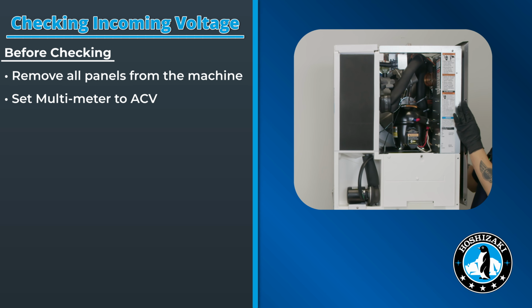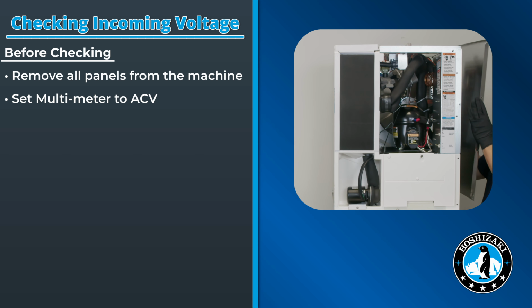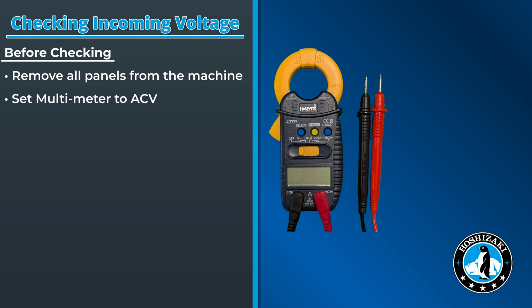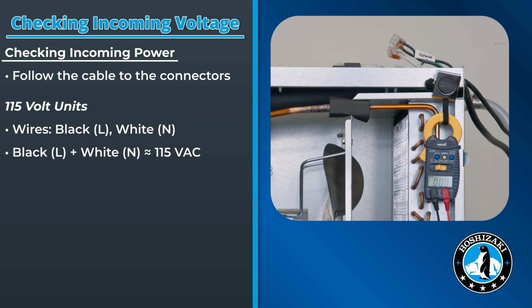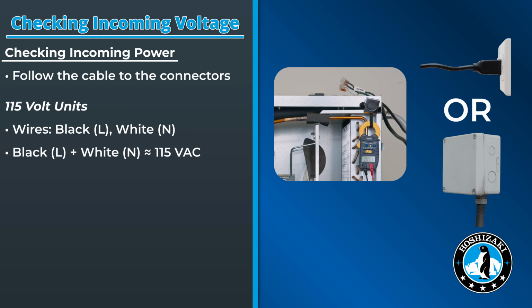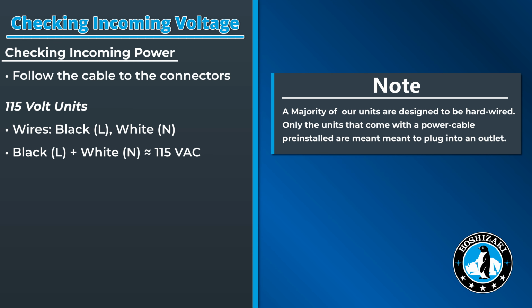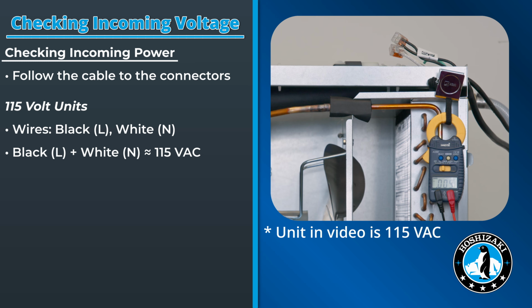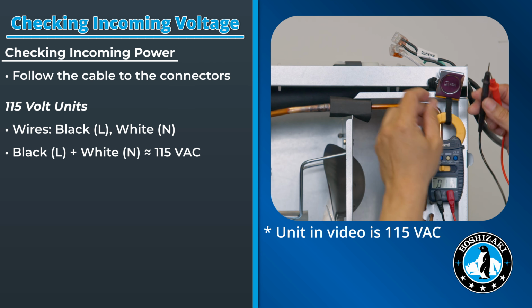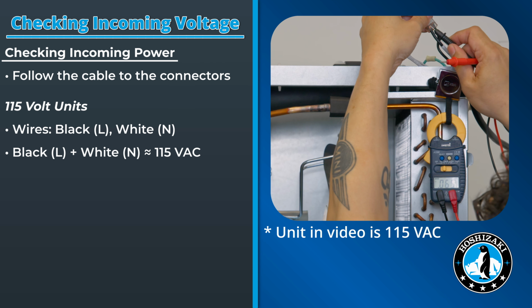Before we begin, remove all panels to gain full access to the machine. Have a multimeter ready, set to AC voltage. The first area we'll inspect is the incoming power at the back side of the machine. Follow the power cables coming from the outlet or the junction box into the unit. Note, all the units that do not come with a plug are meant to be hardwired. At the connector points, verify incoming voltage to confirm the machine is receiving the proper power.